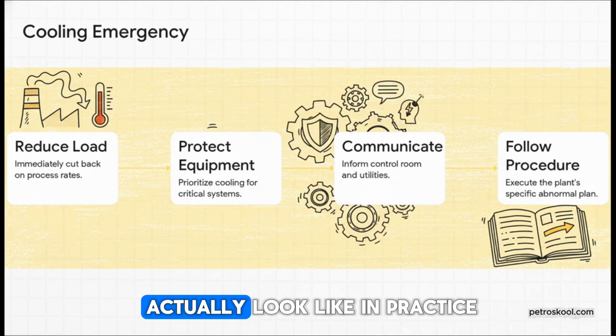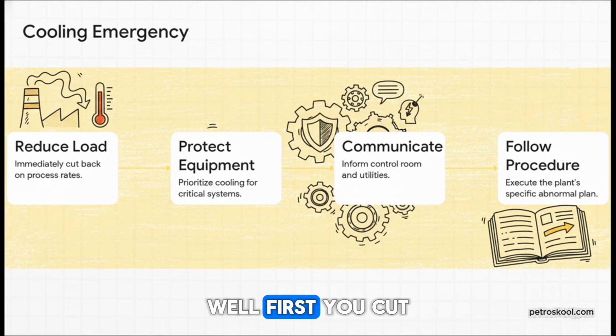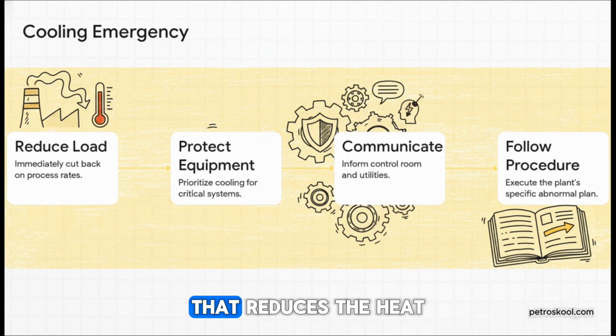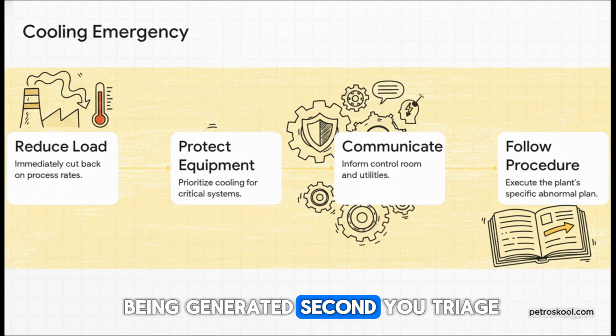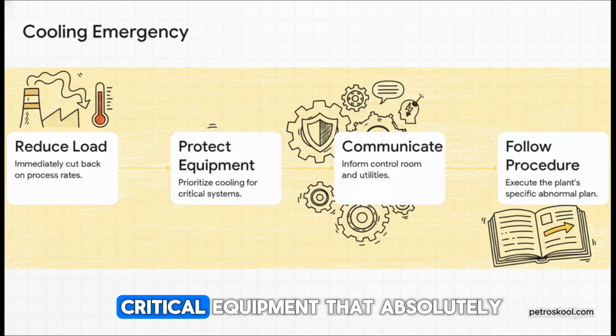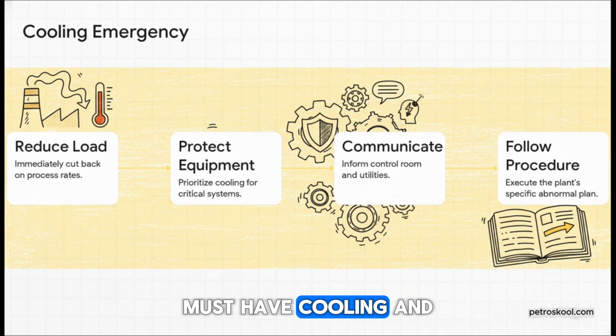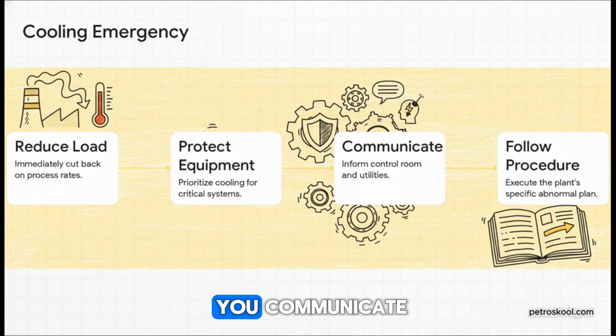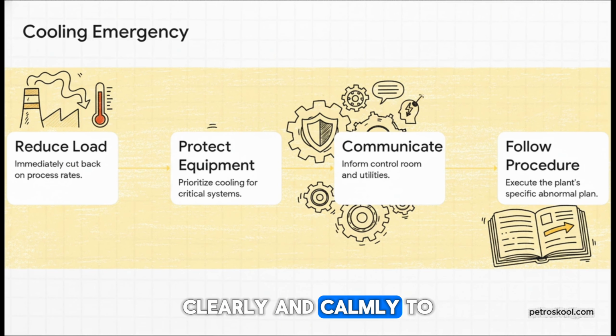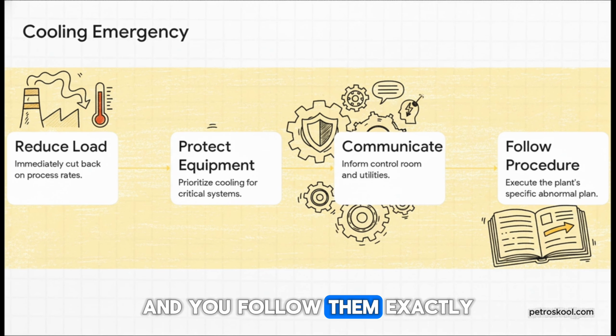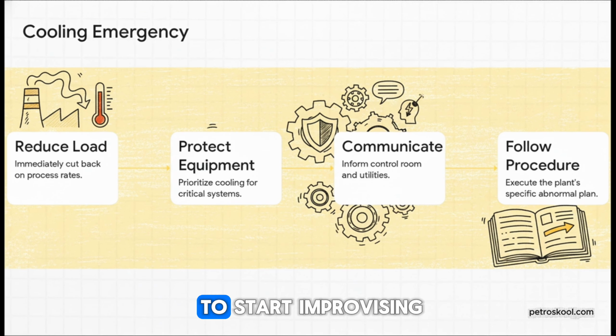So what does that actually look like in practice? First, you cut back your process rates - that reduces the heat being generated. Second, you triage: figure out the most critical equipment that absolutely must have cooling and protect it first. Third, you communicate clearly and calmly to the control room and the utility department. And fourth, you pull out your plant's specific procedures for this and you follow them. Exactly - this is no time to start improvising.